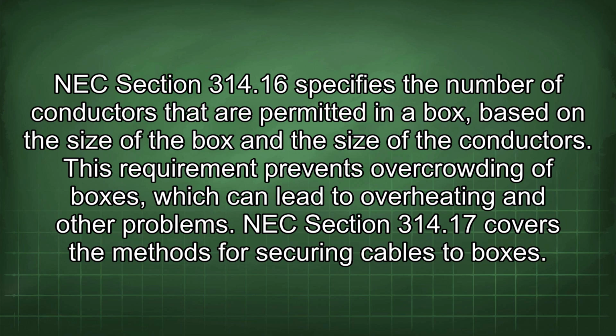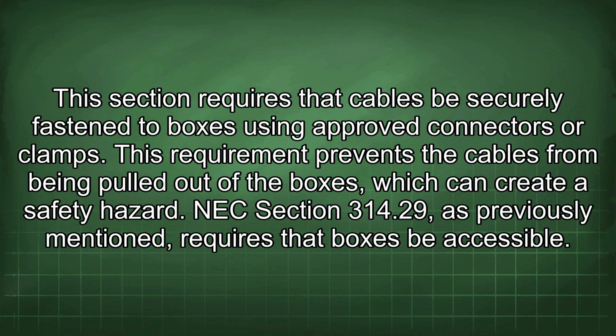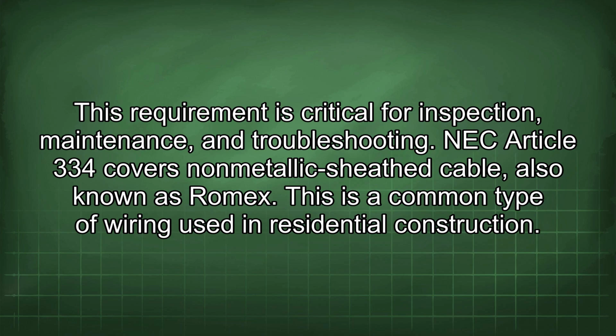NEC Section 314.17 covers the methods for securing cables to boxes. This section requires that cables be securely fastened to boxes using approved connectors or clamps. This requirement prevents the cables from being pulled out of the boxes, which can create a safety hazard. NEC Section 314.29, as previously mentioned, requires that boxes be accessible. This requirement is critical for inspection, maintenance, and troubleshooting.